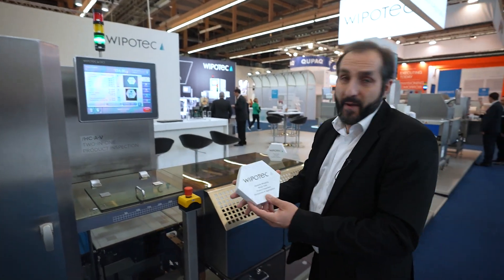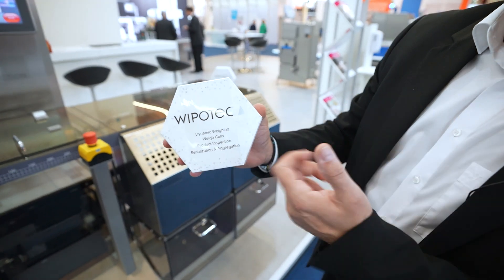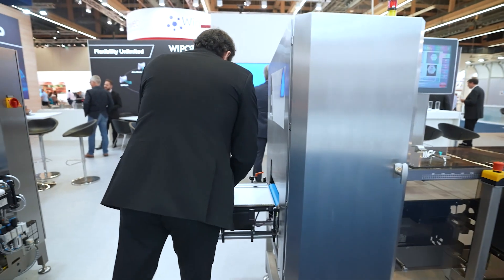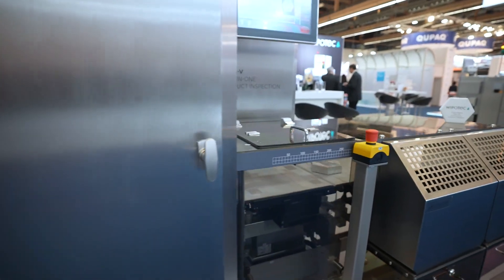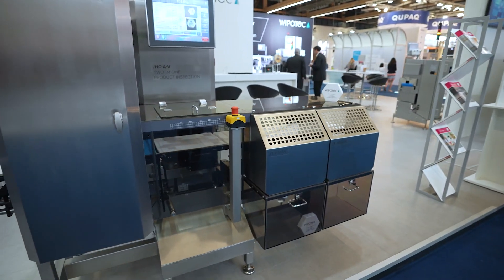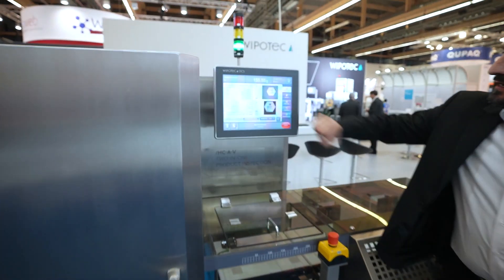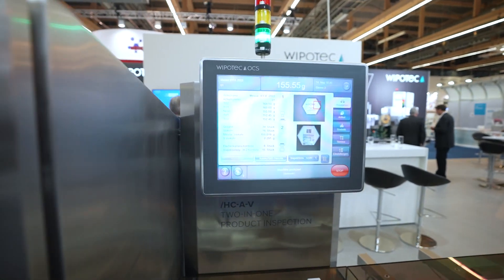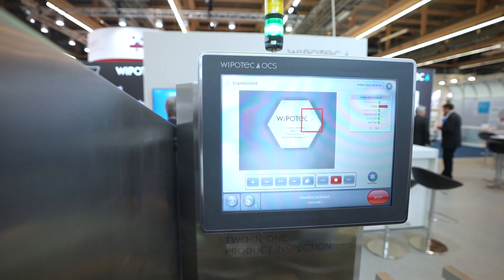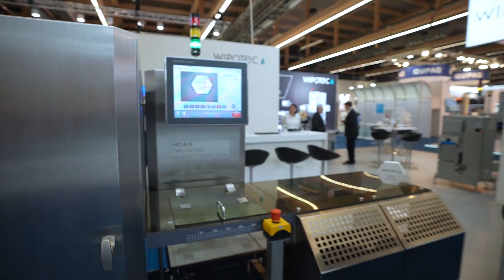Now we have also prepared a bad product — we covered our Wipotec logo here. Let's run this product through and see what happens. The product was ejected automatically, and we can see in our HMI that the region of interest is marked in red, indicating the machine discovered a problem and rejected the product.